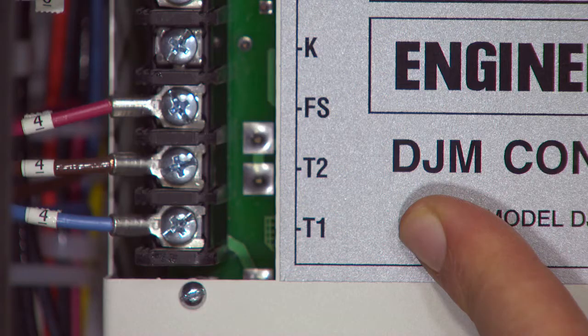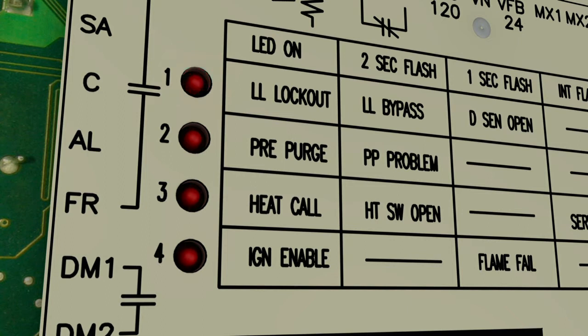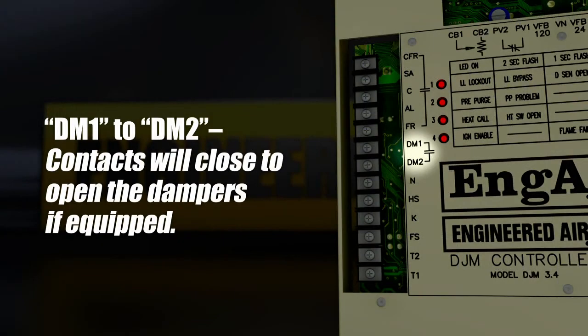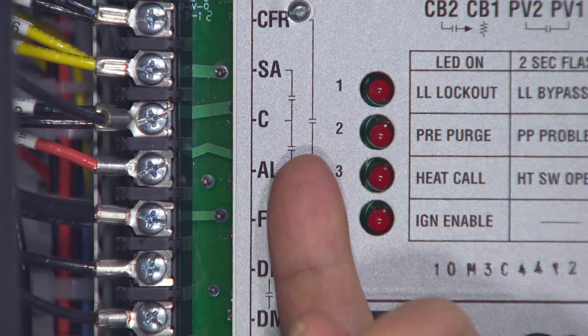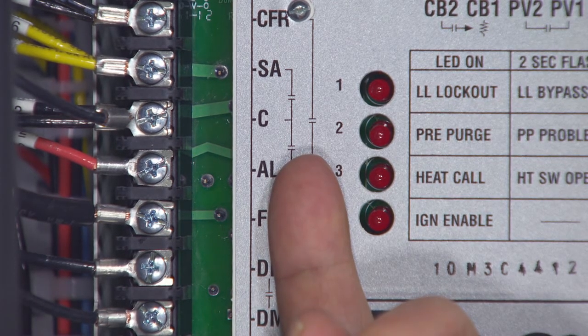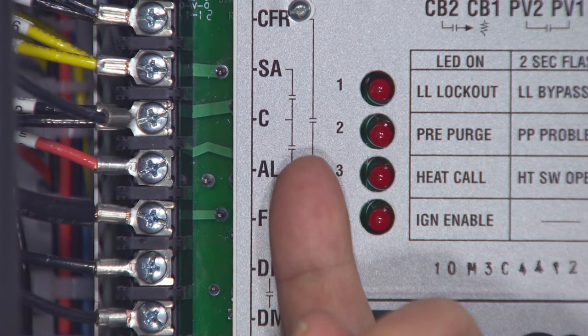Second, heat call. With the power on at T1 and T2, and there is a heat call in the first 30 seconds, the pre-purge starts, the dampers open, and the burner will sequence on in 82 seconds. The supply air blower will start and run in 147 seconds. Now let's go through the DJM-3 sequence of operation. Light 1 will start to do a 2-second flash, indicating the 7-minute low-limit bypass timer is activated. DM1 and DM2 contacts will close to open the dampers if equipped. After about 30 seconds, the C to SA contact will close to start the supply air blower.